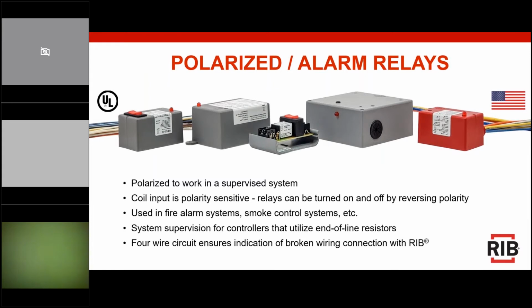Our polarized alarm relay. Here is an example. If you look quite on the far right, there's our red housing. The polarized relays are specifically designed to work in a supervised system, so your coil input is polarity sensitive. These are used in fire alarm, security, and smoke control systems. We do have system supervision for the controllers that utilize end of line resistors. With 4-wire circuits, it helps you make sure that your status is accurately reflected on your fire alarm panel.